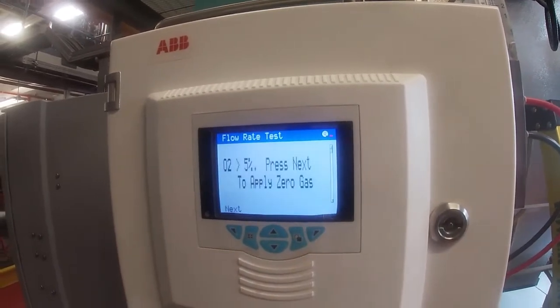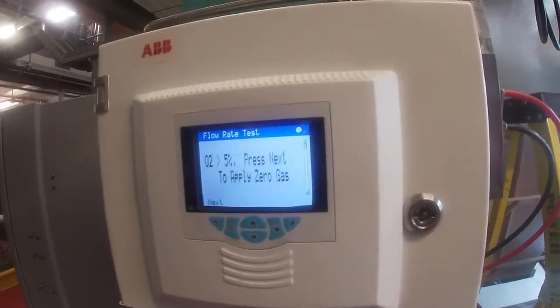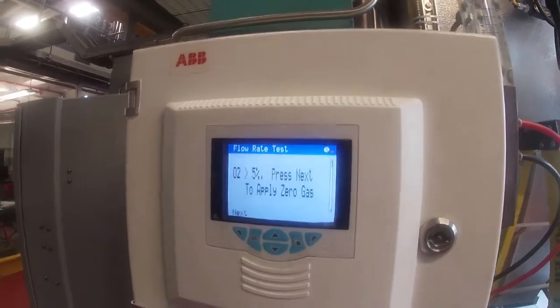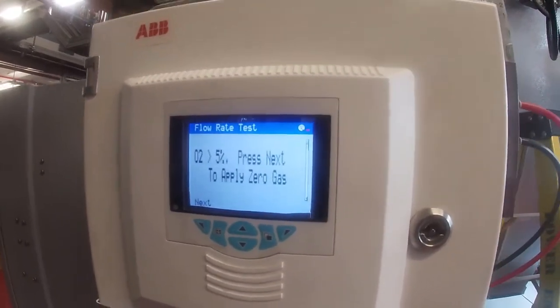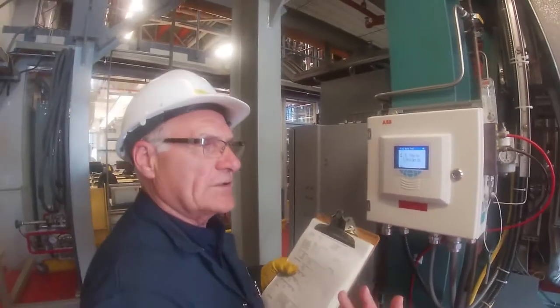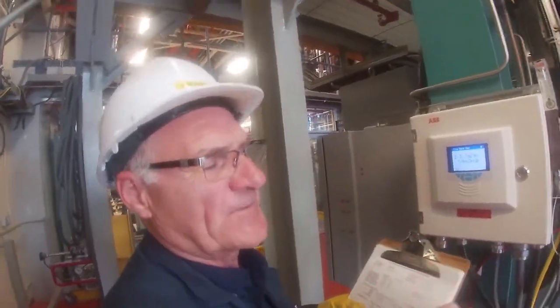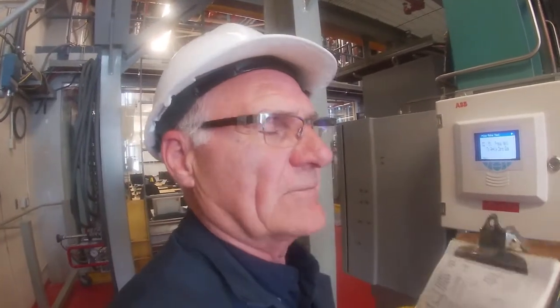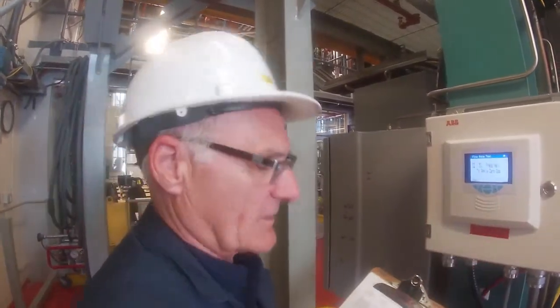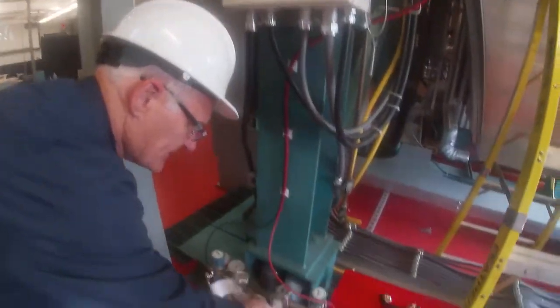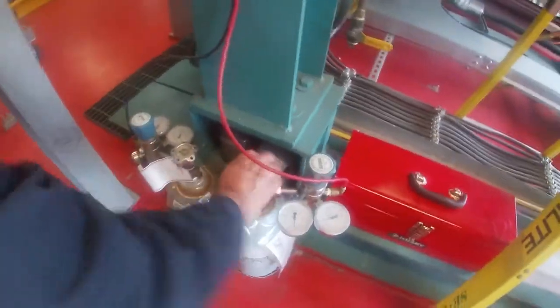Select. Now, it's smart enough to know that right now the oxygen is greater than 5%, so it wants us to use zero gas. If the boiler was running and the O2 was less than 5%, say it's down to 3%, which is where we like it to be, then it would tell us to use span gas. It's just got to find a gas that's way away from where you are now. So we're going to apply zero gas to it. This is the zero gas bottle. I'm going to open this guy up.